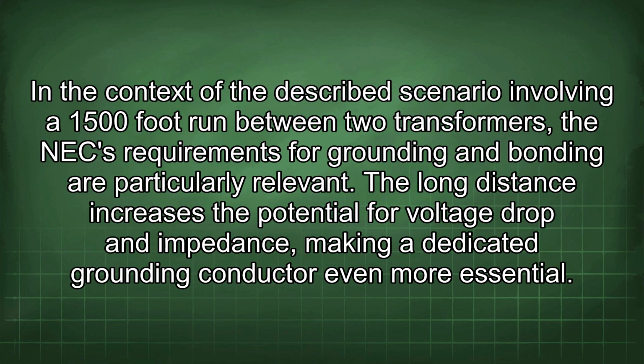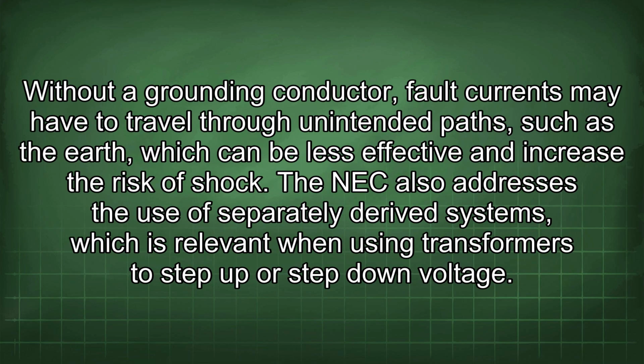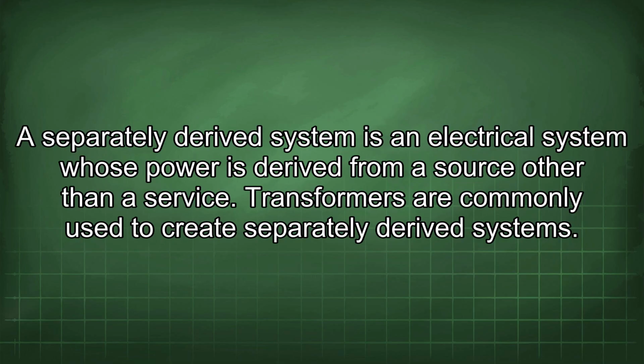In the context of the described scenario involving a 1500-foot run between two transformers, the NEC requirements for grounding and bonding are particularly relevant. The long distance increases the potential for voltage drop and impedance, making a dedicated grounding conductor even more essential. Without a grounding conductor, fault currents may have to travel through unintended paths such as the earth, which can be less effective and increase the risk of shock. The NEC also addresses the use of separately derived systems, which is relevant when using transformers to step up or step down voltage. A separately derived system is an electrical system whose power is derived from a source other than a service.